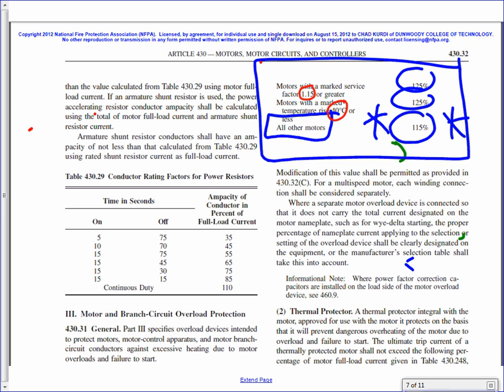Can I get you guys to understand? For overload, the default is 115, 115%. Unless, rule number one, the service factor is 1.15 or larger. Now, what the heck is the service factor? A service factor, guys, SF will be on the motor. This will indicate that the motor can be overloaded for a short period of time, 15%. So if it's a 10 horsepower motor, you can pull 11.5 horsepower out of it for a short amount of time to accommodate an overload condition.